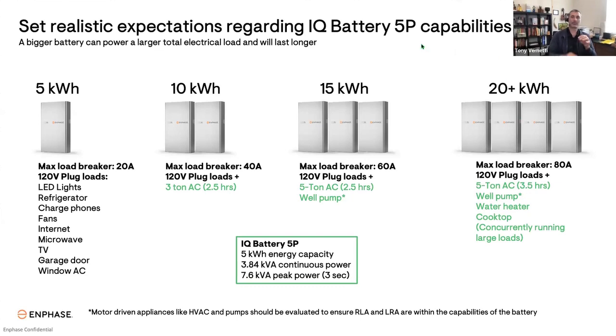Now, if the customer has multiple large electrical appliances and some of those have to run simultaneously, that means they're drawing power at the same time. That's when you're looking at designing systems that are 20 kilowatt hours or larger, so that the battery is going to have enough continuous power to be able to run those multiple large loads simultaneously.